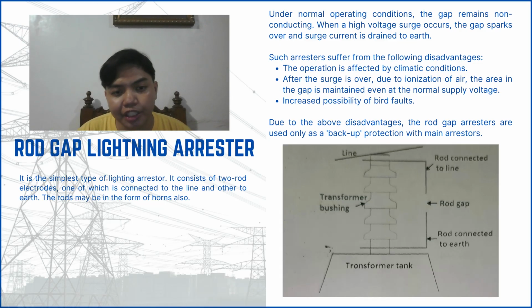It is the simplest type of lightning arrestor. It consists of two rod electrodes, one of which is connected to the line and the other to earth. The rods may be in the form of horns also. Under normal operating conditions, the gap remains non-conducting. When a high voltage surge occurs, the gap sparks over and the surge current is drained to earth. Such arrestors suffer from the following disadvantages. The first is that the operation is affected by climatic conditions. Second, after the surge is over, due to ionization of air, the arc in the gap is maintained even at the normal supply voltage. And lastly, increased possibility of bird faults. Due to the above disadvantages, rod gap arrestors are used only as backup protection with the main arrestors.